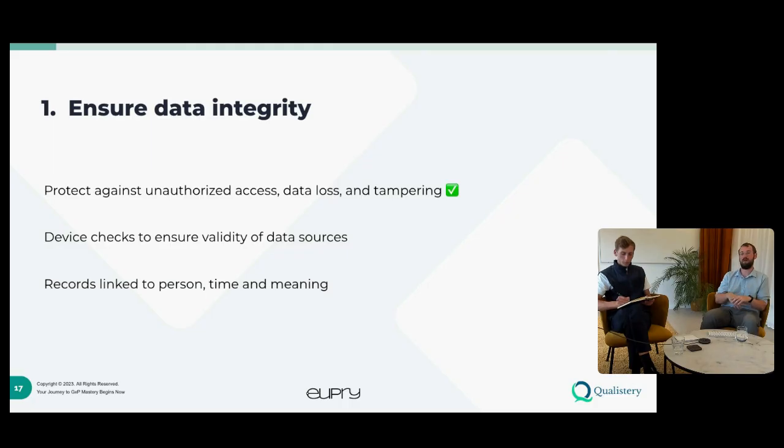If you don't have an automated system, how do you know that the measurements from a specific data logger actually originate from that specific data logger? How do you couple that with the position or the fridge or whatever it's from? And that is again a point at which a system can only do so much in terms of cryptography, encryption, and automated systems. If you don't have a good process of ensuring that you know where that data logger was placed, then the validity of those measurements is actually not valid anymore, because they might not originate from the unit that you're trying to measure. So again, a system can only do so much.